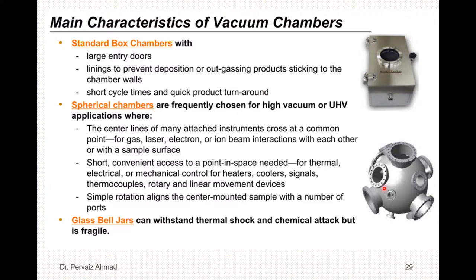Then we have the spherical chamber. Spherical chambers are more frequently chosen for high vacuum or ultra-high vacuum applications, where the central lines of many attached instruments cross at a common point. Multiple instruments can be attached simultaneously to multiple channels. This allows gas, laser, electron, or ion beam interactions with each other or with a sample surface. It provides short, convenient access to a point in space needed for thermal, electrical, or mechanical controls — for heaters, coolers, signals, thermocouples, or rotary and linear motion devices.